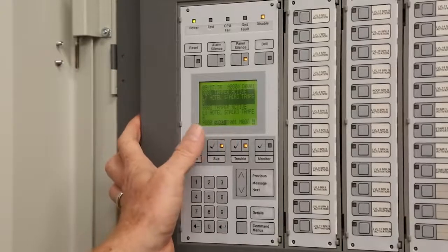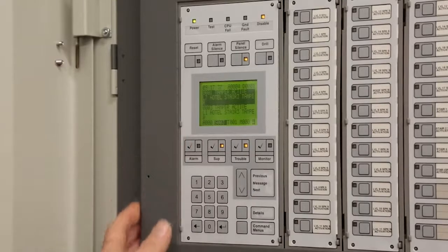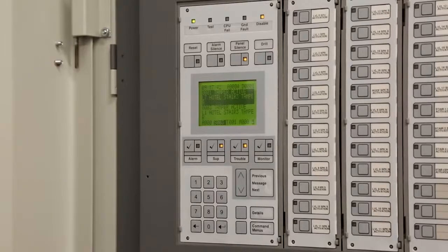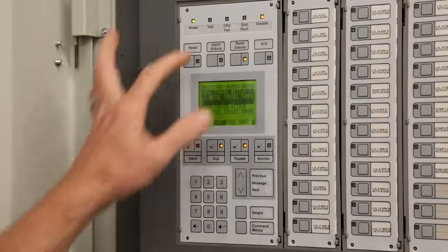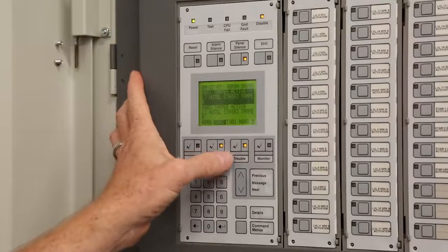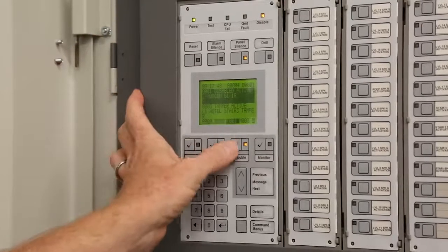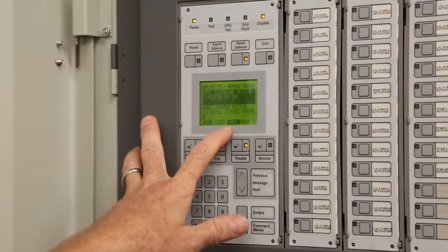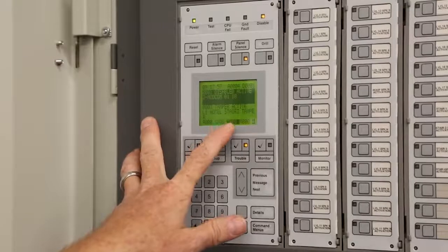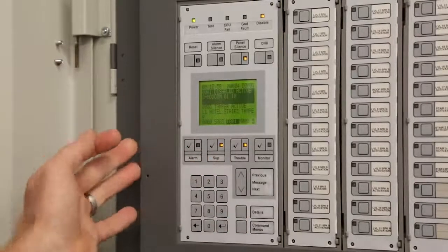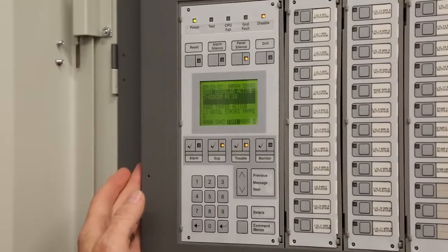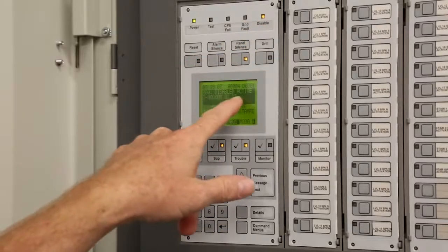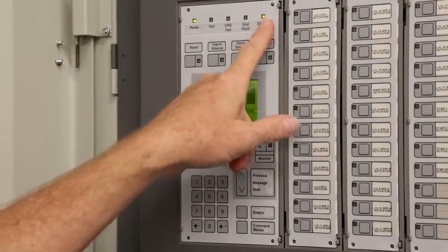Troubles would be any abnormal condition, and it could be that the device is not responding, could be an open circuit, or it could be like we have right now, disabled. For instance, right now you can pull up your troubles by just hitting the button right there, and you can scroll up and down. Right now, if you see there's a T right there that represents troubles, there's only one. Right now, it says Modcom. That's because I have the dialer offline, so it won't report right now. And also, if we have anything disabled, like I have this disabled, it says disable active, and your disable light's on up here, okay?